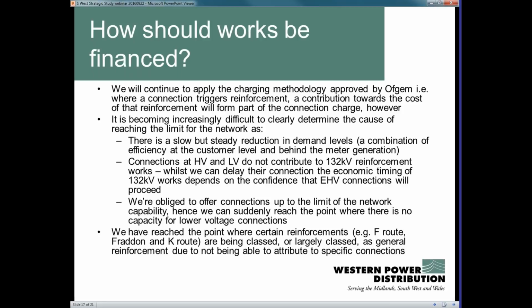So we're seeing that steady increase in HV and LV connections, which slowly eats into any capacity we have and can then trigger reinforcement. Finally, we're obliged to give an offer up to the limit of the network. So once an offer's been made and that generation goes ahead, if we then see a reduction in demand levels, that will trigger reinforcement, and you can't really attribute it to a generation retrospectively.